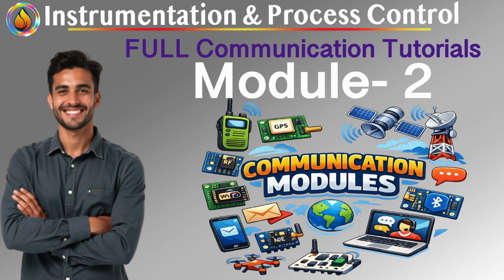Two-wire versus four-wire, half-duplex versus controlled duplex. RS485 supports two wiring philosophies and each reflects a different control mindset. In a 2-wire system, the same pair is used for transmit and receive. Devices take turns talking. Communication is half-duplex. This is the most common industrial implementation because it uses less copper, simplifies installation, forces clean turn-taking. In a 4-wire system, one pair is dedicated to transmit, one pair is dedicated to receive. Communication behaves like full duplex, but only in one direction per role. Here, one node is always the master and others are always slaves. Slaves never hear each other. This avoids accidental contention entirely and is favored when reliability beats flexibility.